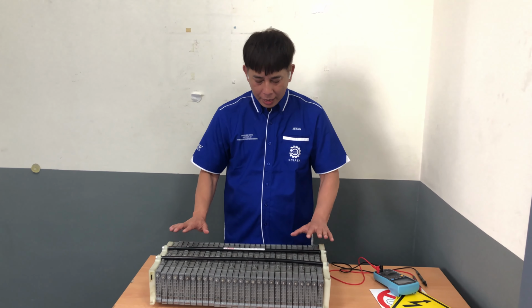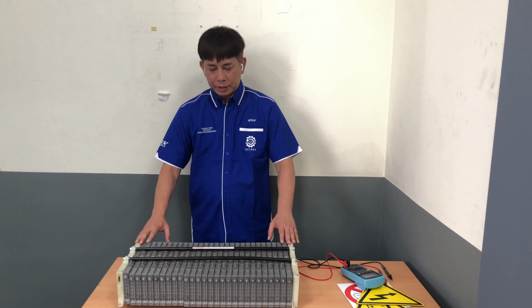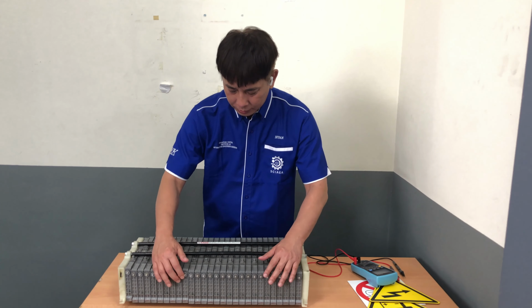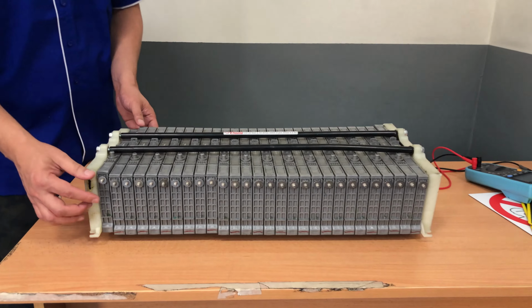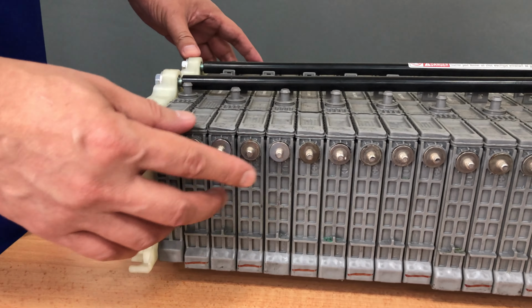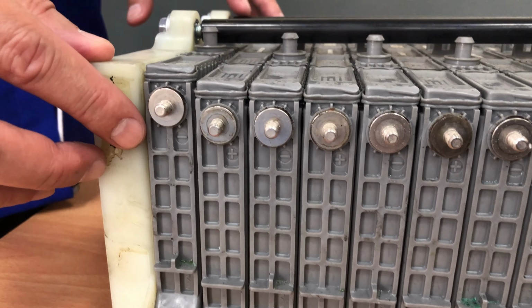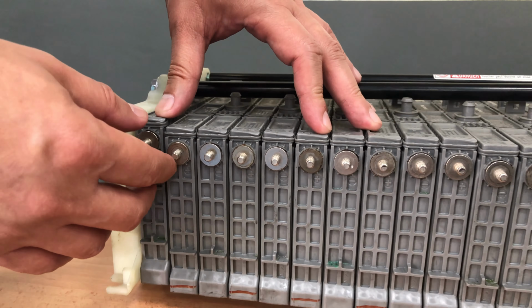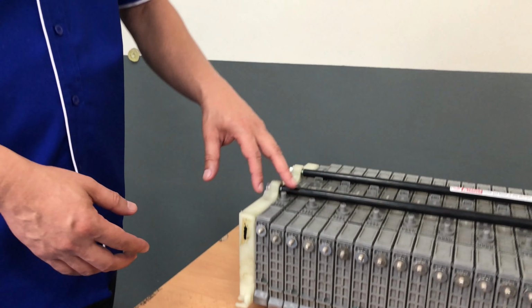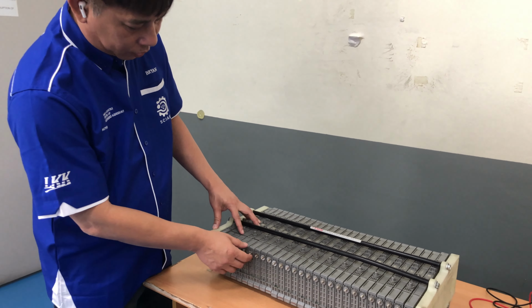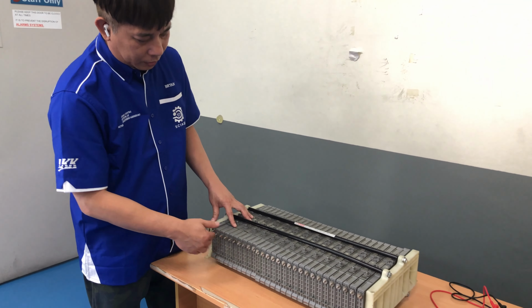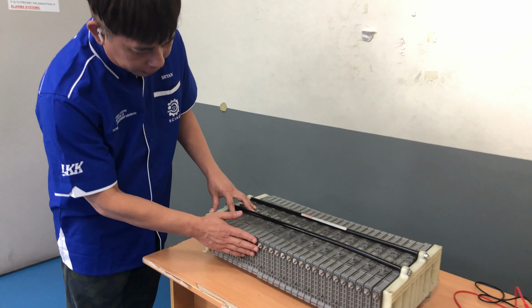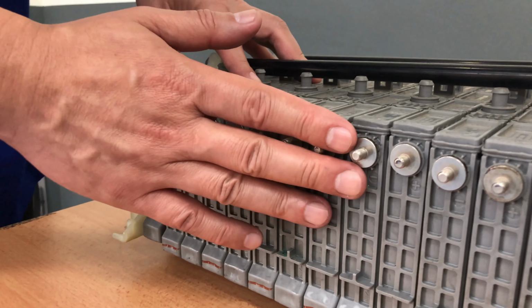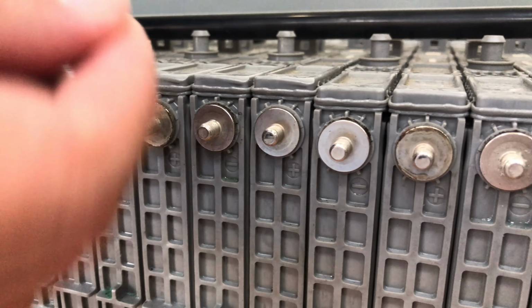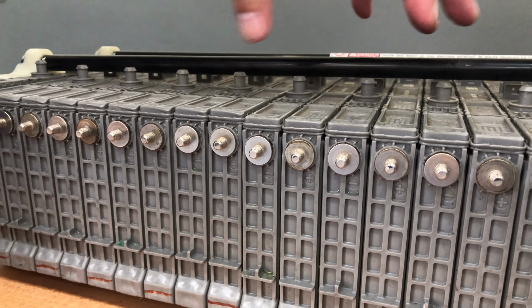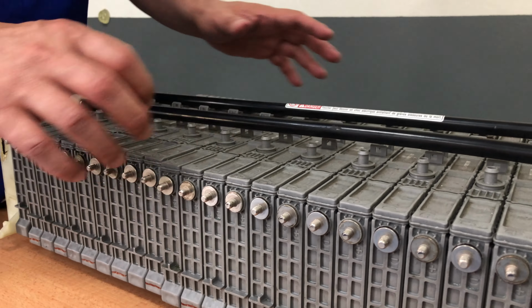From there you will be able to know which cell is faulty. Now, other things as part of the servicing is that you need to clean all these terminals, the cell terminals, and you do not use spray. You cannot use WD-40 because it has conductivity, it is able to conduct electricity. So what we would suggest is to clean all this via sandpaper and then brush it off, and then you can actually air blow it and make sure that no dirt forms around on these grooves.